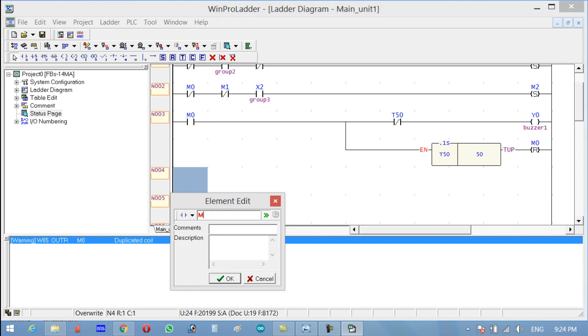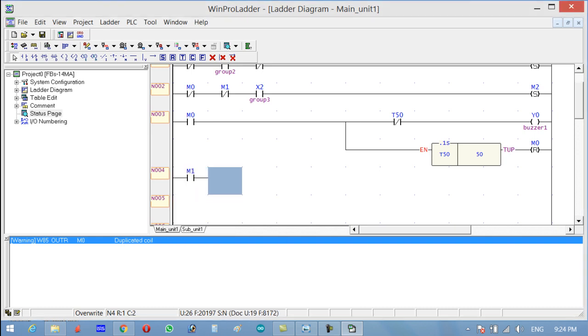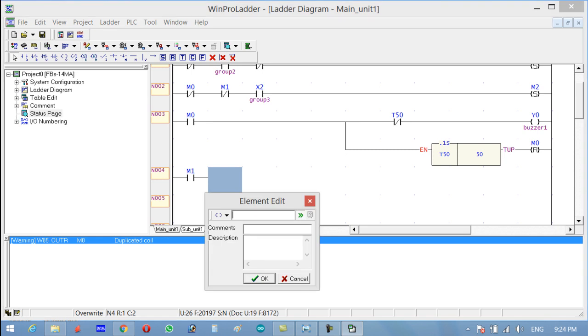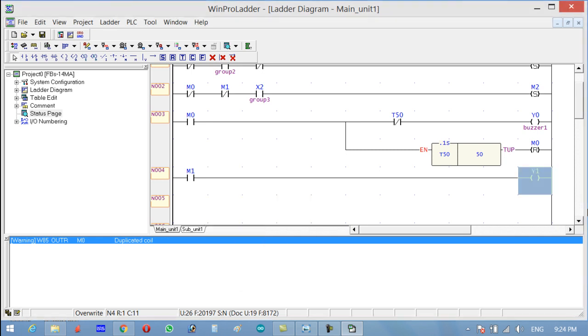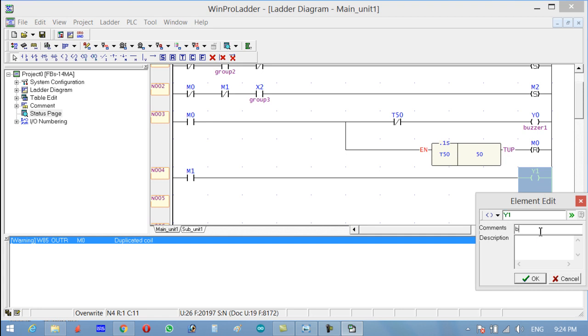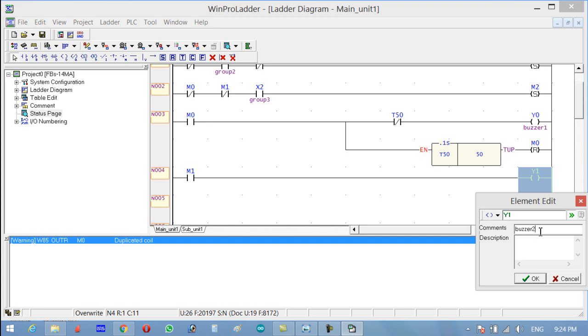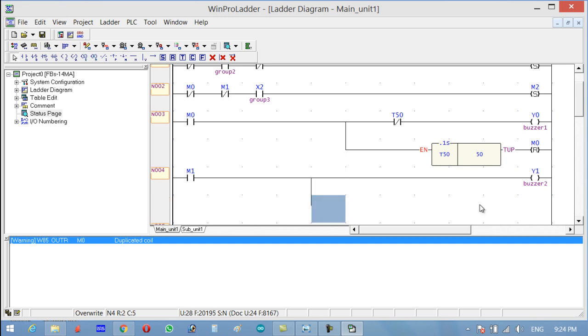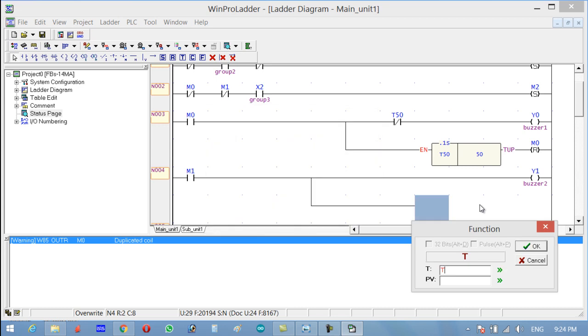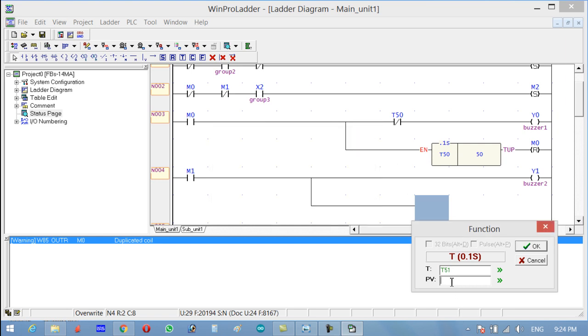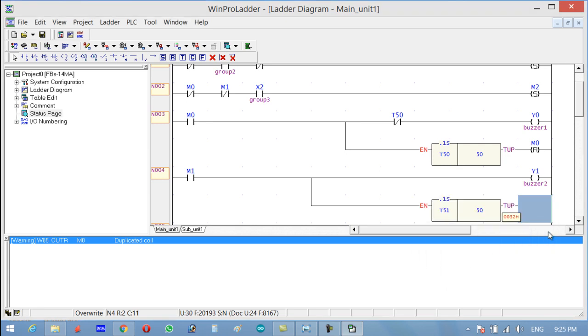Now go look for M1. Press the keyboard shortcut and write Y1 — this is the buzzer for Group 2. Press V on the keyboard, then F for function, select timer, and we'll use timer T51. Enter the preset value 50 for 5 seconds, then reset and write M1.